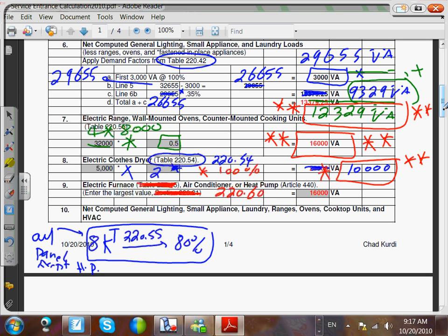In this case, these are also called non-coincidental loads, right? They wouldn't run by design. They're not meant to run together. You interlock them electronically, where one will go and the other will not go. So in this case, that will be non-coincidental loads. In a residential building, guys, non-coincidental loads are mainly heat and cool. You can't heat and cool the building, residential building or any building, for the most part, at the same time. Okay. So you need to go find the heat in your building and the cool in your building.